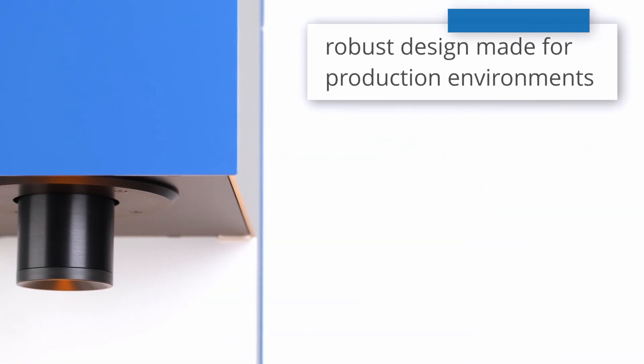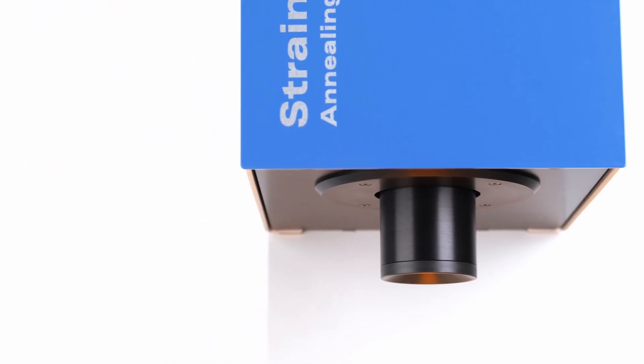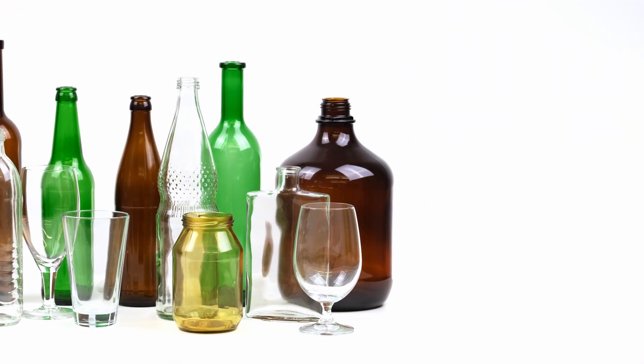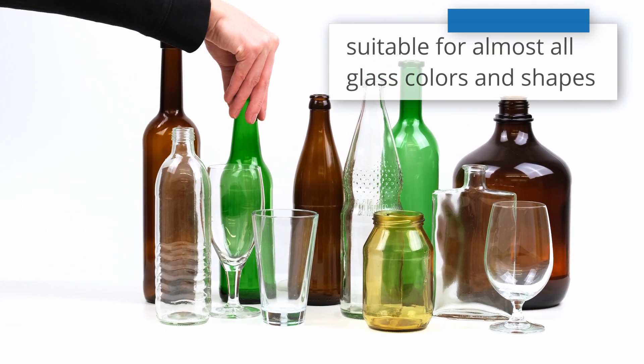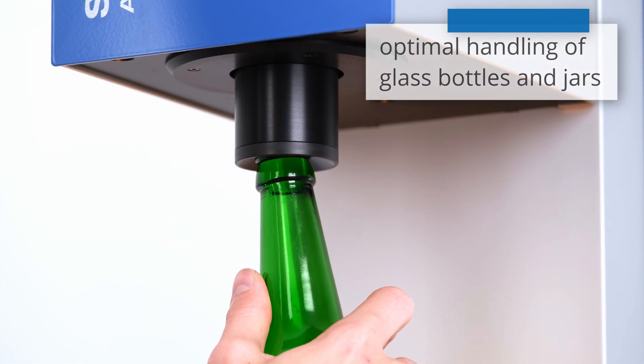The sensitive optics are well protected and therefore suitable for daily use in production environments. Measure the residual stress precisely and independently of the glass color. The robust lens protection tube supports the operator in aligning the sample for optimal measurement.